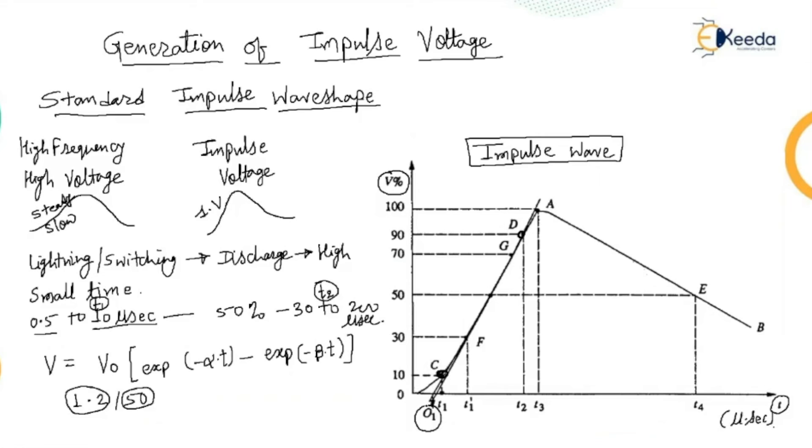So, 1.25 times the interval between times T1 and T2 corresponding to points C and D, that defines as the front time, that is 1.25. The point E is located on the wave tail corresponding to 50%. Corresponding to 50%. So you can see the voltage of 50% is reached. So, this particular point, that is point E and its projection on the time axis is T4. So, O1 T4 is defined as the fall or tail time.